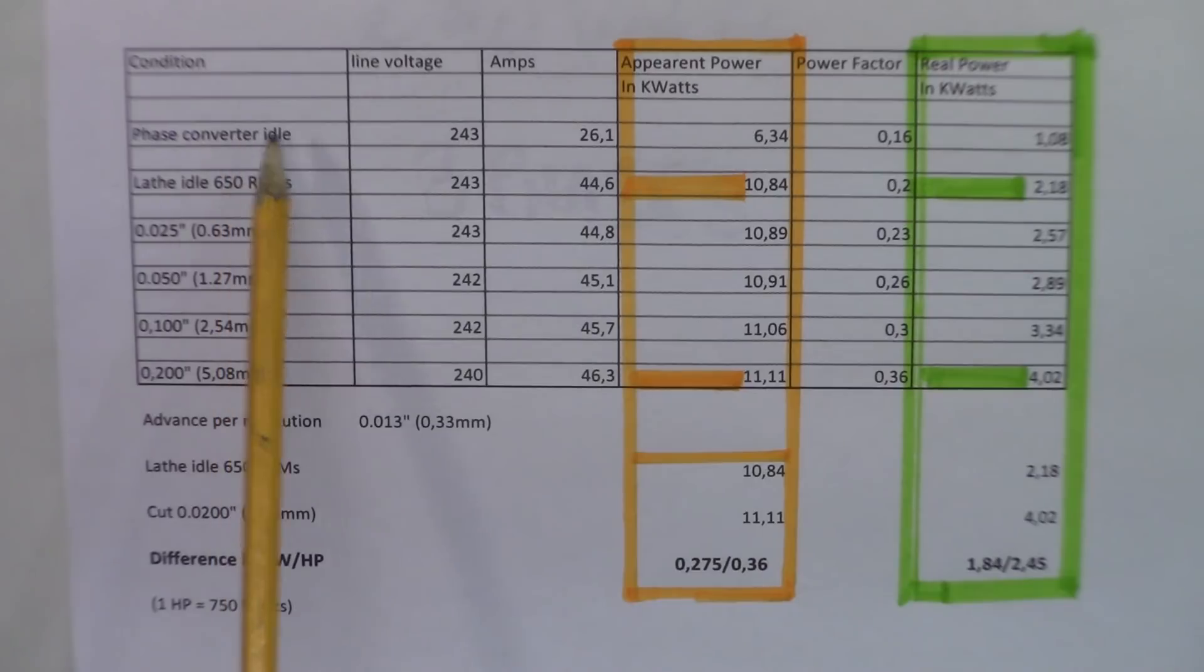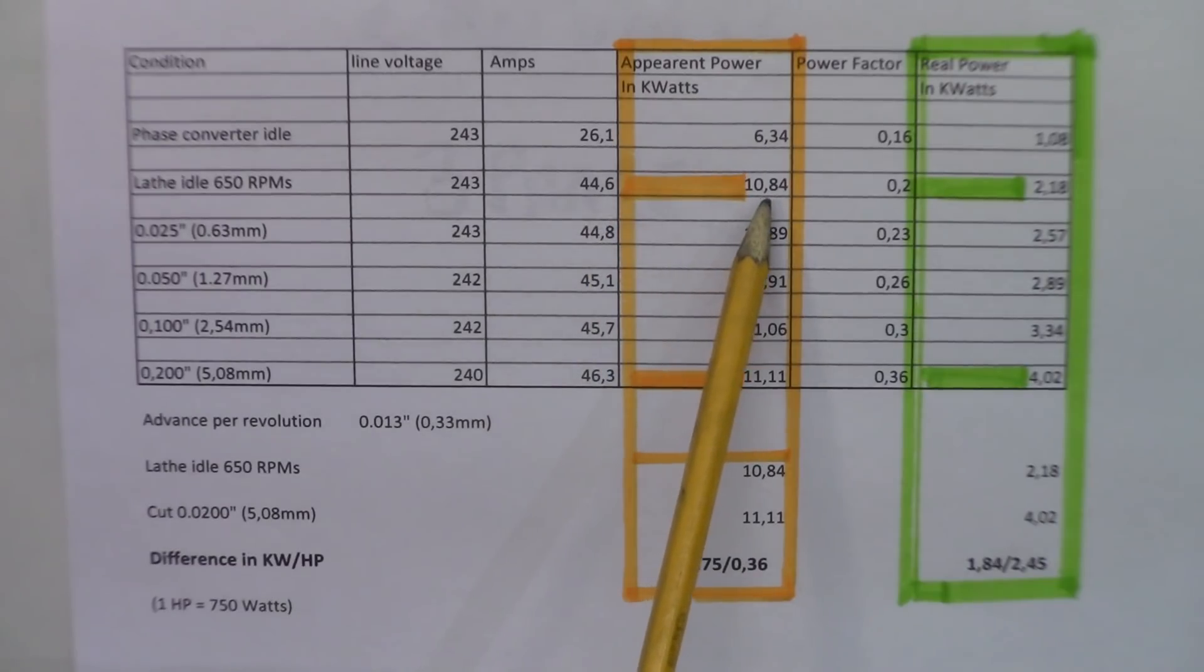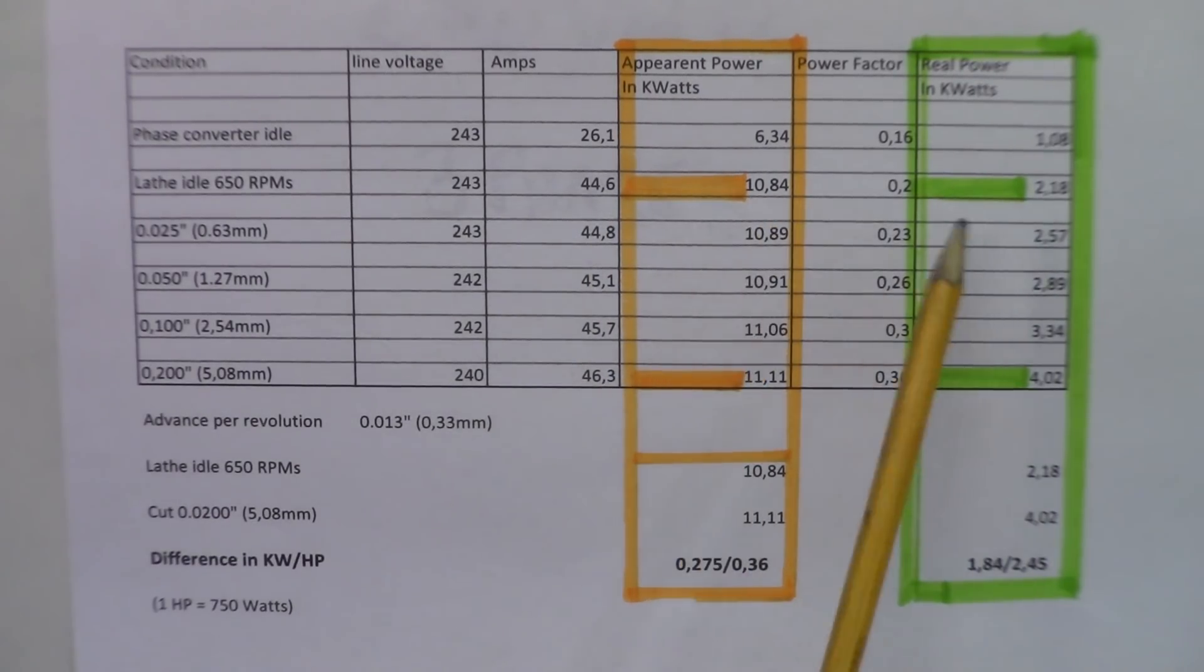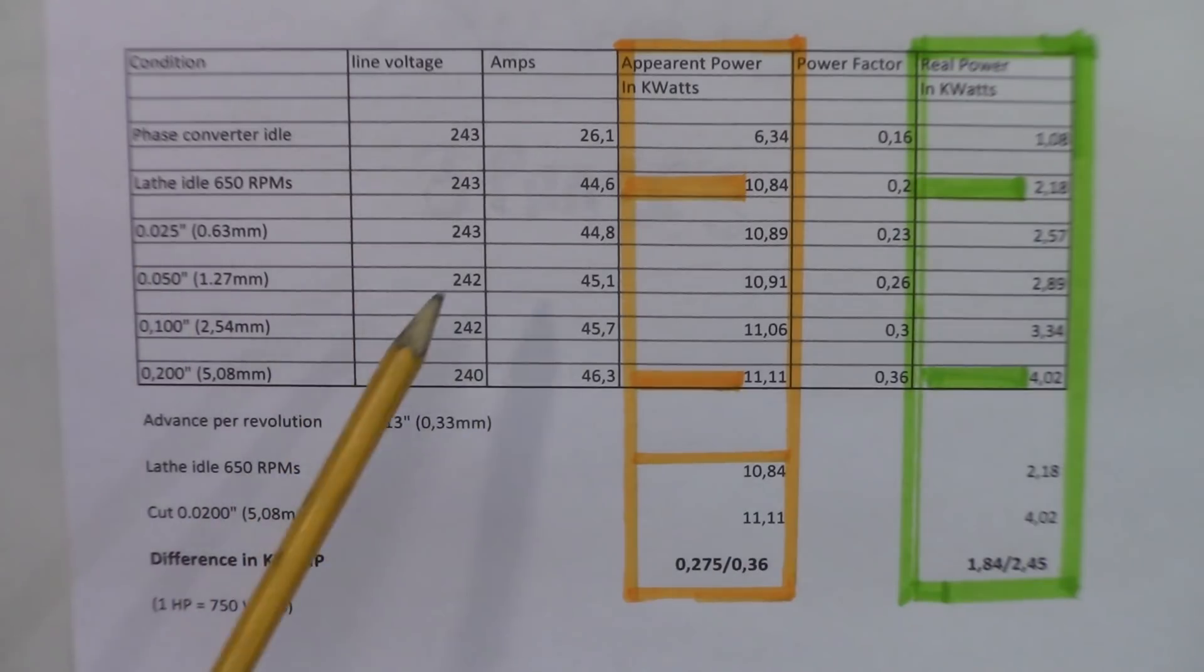This is not exactly relevant to today's testing, but we'll be just putting the lathe under power. The motor is idling 650 RPMs, so the figures will change here quite drastically. We're getting like 10 kilowatts of consumption, but you bring back the power factor to a more realistic figure, and it's going to give you 2.18 kilowatts, which is a big difference. So the different cuts here, which I compiled, let's say 10 kilowatts, 10.89, up to 11.1 kilowatt here, and the real power will be like 2.18 to 4.02 after just being corrected with the power factor.